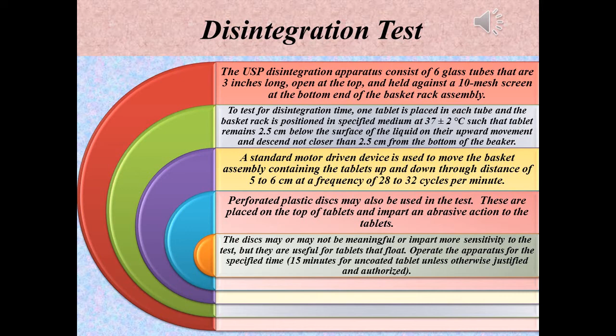A standard motor driven device is used to move the basket assembly containing the tablets up and down through a distance of 5 to 6 cm at a frequency of 28 to 32 cycles per minute. Perforated plastic discs may also be used in the test. These are placed on the top of the tablet and impart an abrasive action to the tablet. The discs may or may not be meaningful or impart more sensitivity to the test, but they are useful for tablets that float. Operate the apparatus for the specified time, 15 minutes for uncoated tablets, unless otherwise justified and authorized.